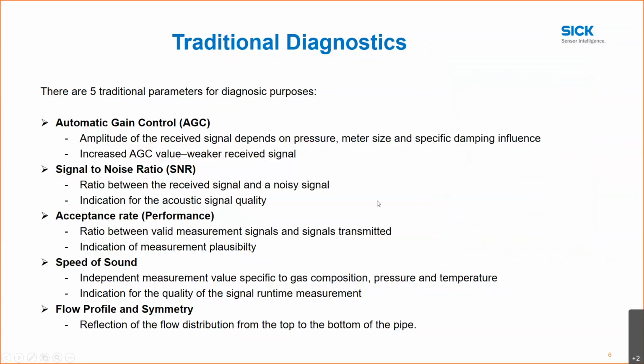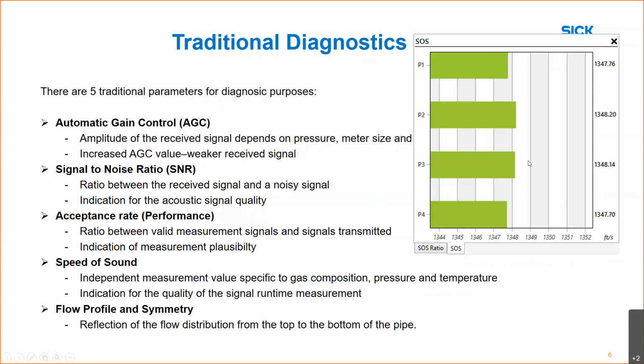Speed of sound is an independent measurement value specific to the gas composition's pressure and temperature. It's an indication of the quality of the signal. If we look here, we see that in this example, our speed of sound is 1347, 1348, 1347. The speed of sound being calculated by these individual paths should all be within 2 feet per second of each other. If it's not, it's again an indication of something that's interfering with the signal going back and forth and causing the transit time to change, and should be investigated.